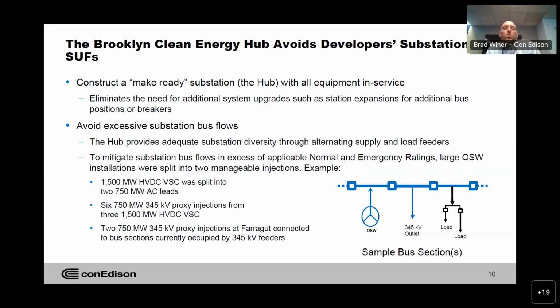What, if any, cost responsibility will developers bear for the development of the proposed hub? I want to separate a couple of things. From the perspective of the hub itself, as proposed in our petition, developers are not responsible for reimbursing the cost of the hub. Clearly, during the NYISO interconnection process, as I mentioned earlier, there will be a limited number of system upgrade facilities identified—nominal compared to requirements if you were to interconnect into other areas or existing substations. Some of those may include protection, control, metering, etc. Those costs will be assigned to the developer through the interconnection process and captured in the interconnection agreement. That will be the limit of the cost responsibility for the hub.